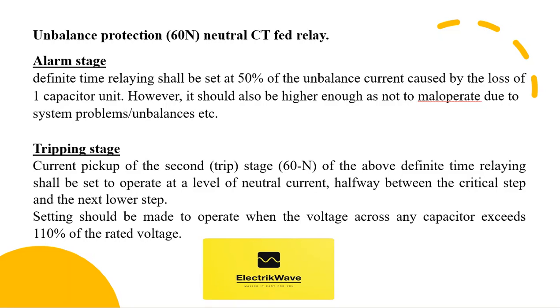The critical step is the number of units that will cause a group over voltage in excess of the manufacturer's recommended maximum continuous voltage. However, the setting should be made to operate when the voltage across any capacitor exceeds 110% of the rated voltage. The timer unit shall be set for a delay sufficient to avoid false operations due to inrush, outrush, ground faults on a line, lightning, switching of nearby equipment, and the closure of the circuit breaker. However, it should be as fast as possible to facilitate high-speed operation for rack faults. The trip stage of the protection shall trip and lock out respective circuit breakers. The lockout function shall short circuit the CT secondary to avoid damage to the loading resistor. The CTs shall have an adequate knee point voltage for single phase currents, shall have low over voltage pickup, and shall have a third harmonic rejection circuit to render it insensitive.